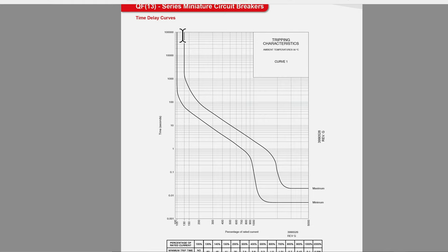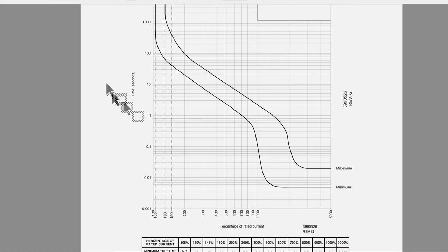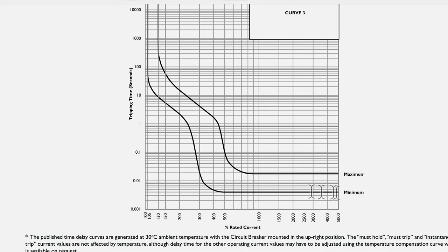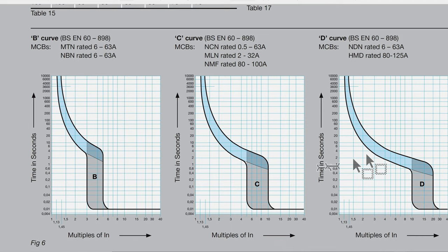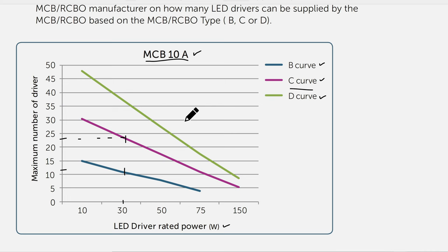These tripping curves are provided by the manufacturer, so you'll need your circuit breaker model number to find the time-delay tripping curves for review. On this particular manufacturer's curve, the horizontal axis is labeled as percentage of rated current — so 500 means five times the rated current, meaning 50 amps for a 10-amp breaker. The tripping curves are often shown as a minimum and maximum band due to something called hysteresis, so we'd expect a trip anywhere between those two lines.